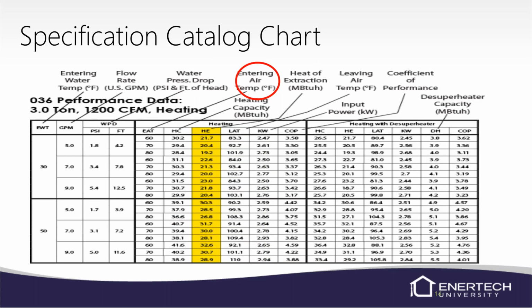Entering air temperature, that's your return air temperature on the unit. If you've got a water-to-water unit, that'll say entering or leaving load temperature. But for the air side of things, we look at entering air temperature. We do have a correction factor, so if you're outside of those ranges, in the back of all of our manuals, there is a correction factor you can use. I don't normally use the correction factors unless my numbers are off a little bit.